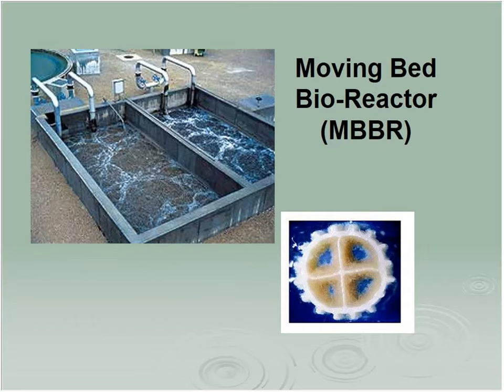And the last, but not necessarily the greatest, iteration of the process, again, these are for situations where you have to upgrade your plant. We're talking, you've exceeded that 80% or whatever it is, and they say you've got to upgrade to treat more. Well, most plants were built down by the river at one point in time, and you may have some land, and you may not. Well, this is for places that have no place to go. And since you have no land for more reactors or clarifiers, what you do is you combine a fixed film process with a suspended growth process by throwing in some sort of media into your tanks. Now you've got growth on the media, you've got the suspended liquor swimming around too, so you can process more for a given tankage than you normally could.